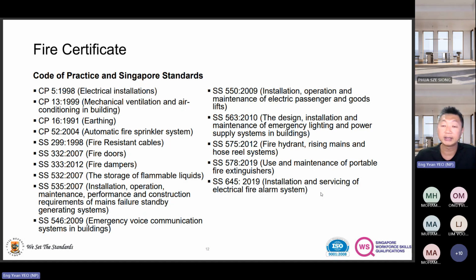In terms of all items installed in the building, they will be tested, except for detectors. What's the percentage - do we need to test 100% of detectors every year? No, no need. What's the percentage? 20% every 5 years - correct, so it's 20%.